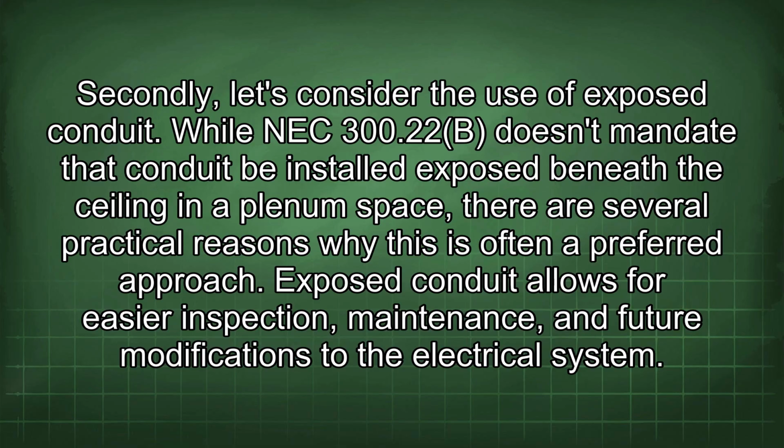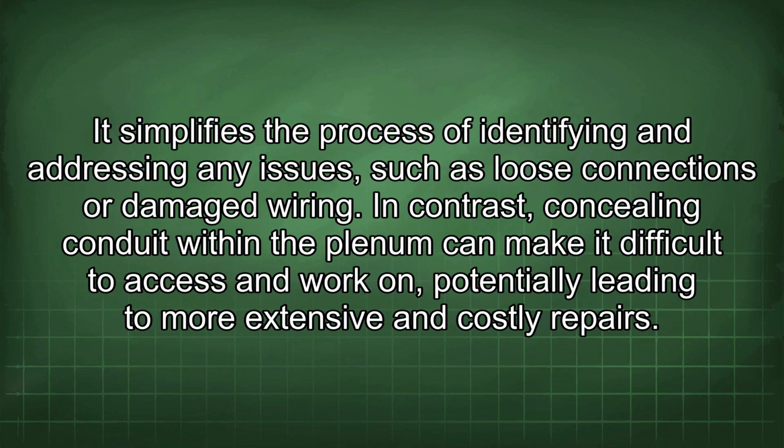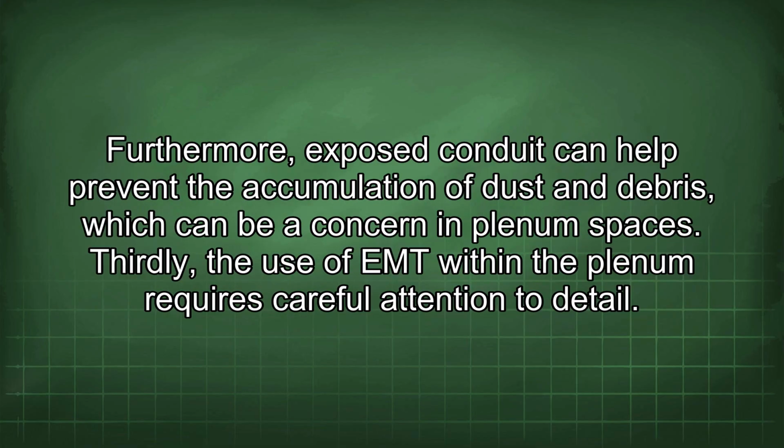Exposed conduit allows for easier inspection, maintenance, and future modifications to the electrical system. It simplifies the process of identifying and addressing any issues, such as loose connections or damaged wiring. In contrast, concealing conduit within the plenum can make it difficult to access and work on, potentially leading to more extensive and costly repairs. Furthermore, exposed conduit can help prevent the accumulation of dust and debris, which can be a concern in plenum spaces. Thirdly, the use of EMT within the plenum requires careful attention to detail.